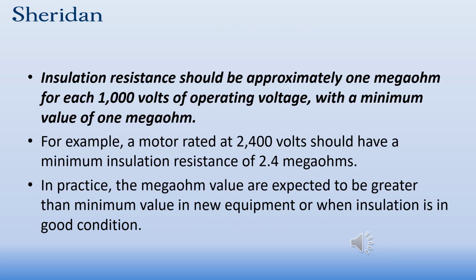So what kind of reading should you get? The insulation resistance to chassis or ground should be approximately 1 megohm for each 1,000 volts of operating voltage, with a minimum value of 1 megohm. It should never, ever be below 1 megohm. If it is, then the piece of equipment is no good. Let's say, for example, I was to take a 2400 volt motor or transformer. The minimum resistance would be 2.4 megohms. However, in practice, if you have a piece of equipment that is new or the insulation is good, you really should have something much higher than this.